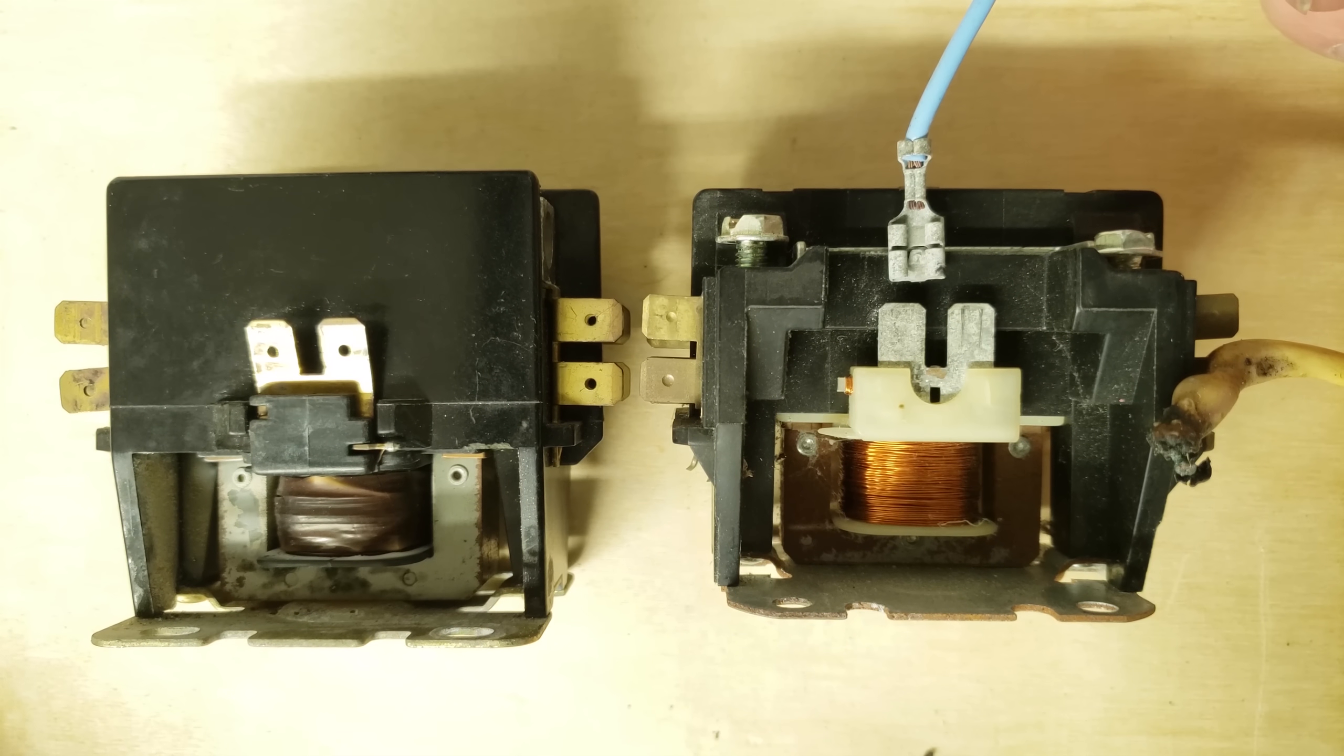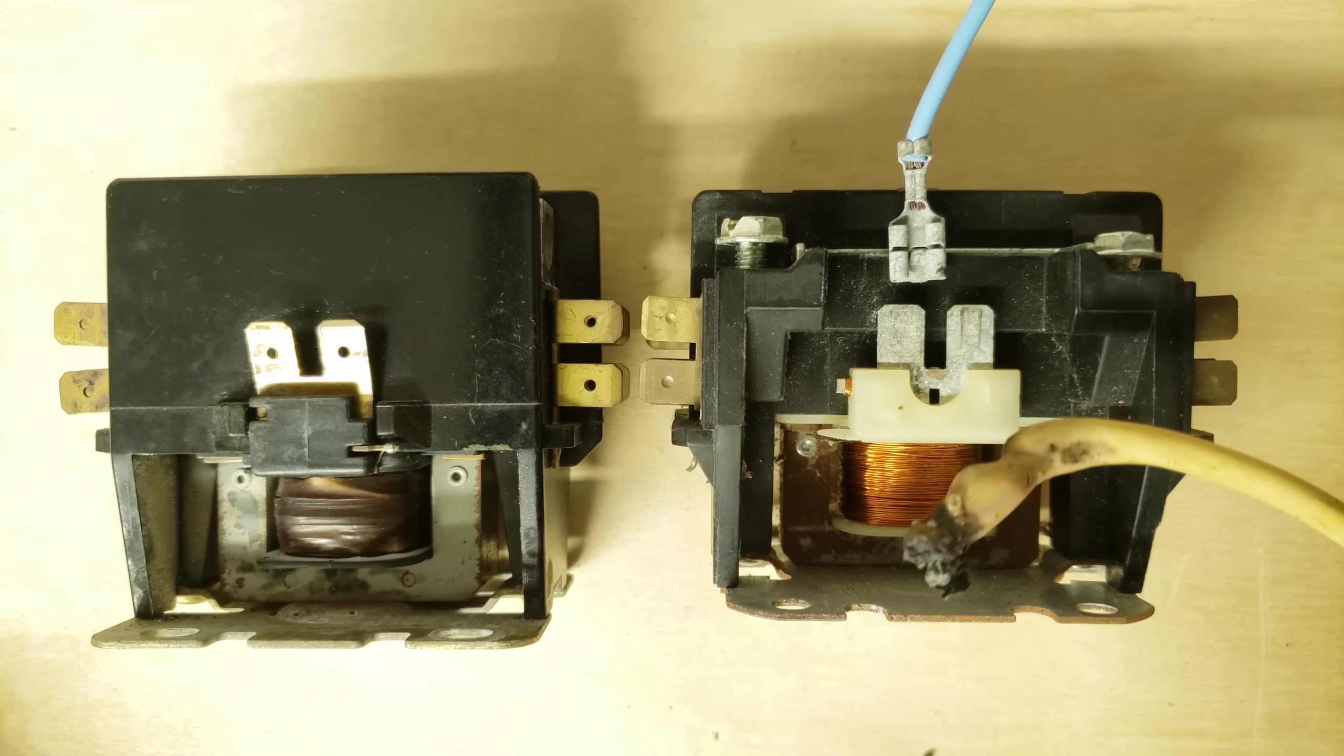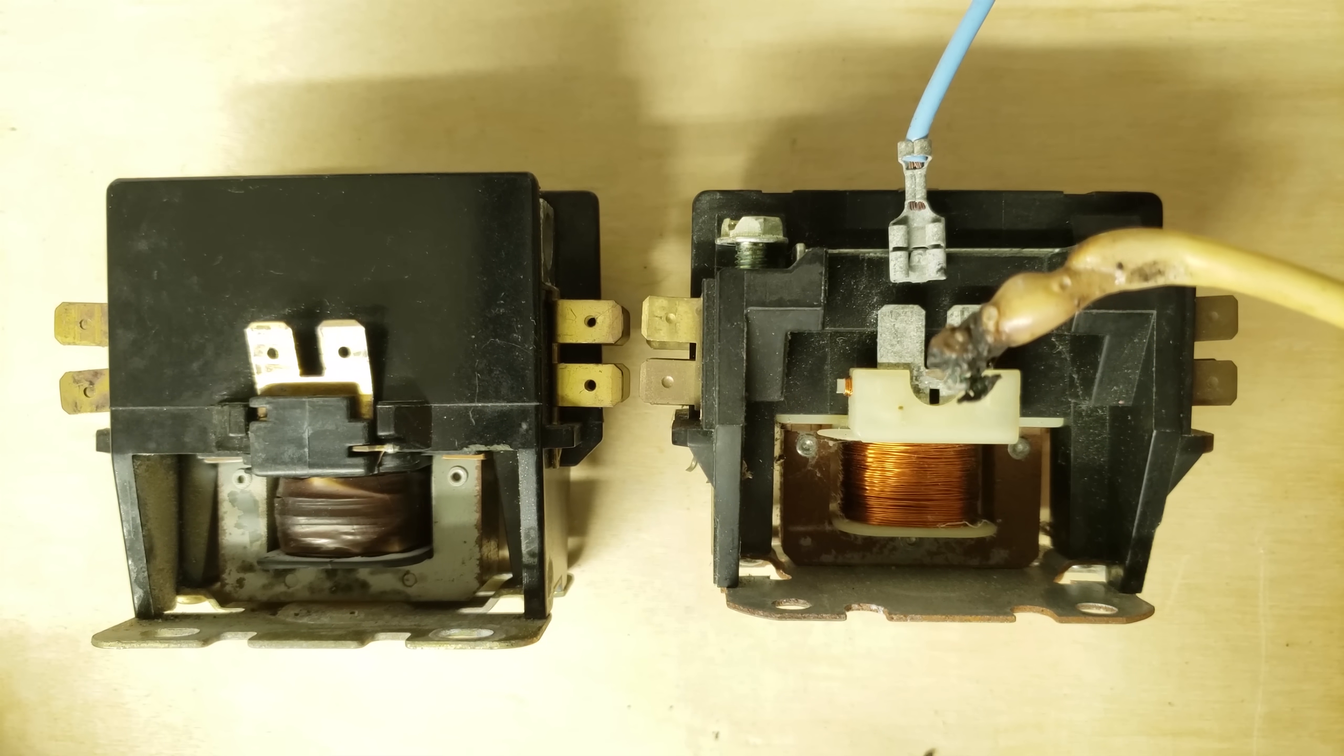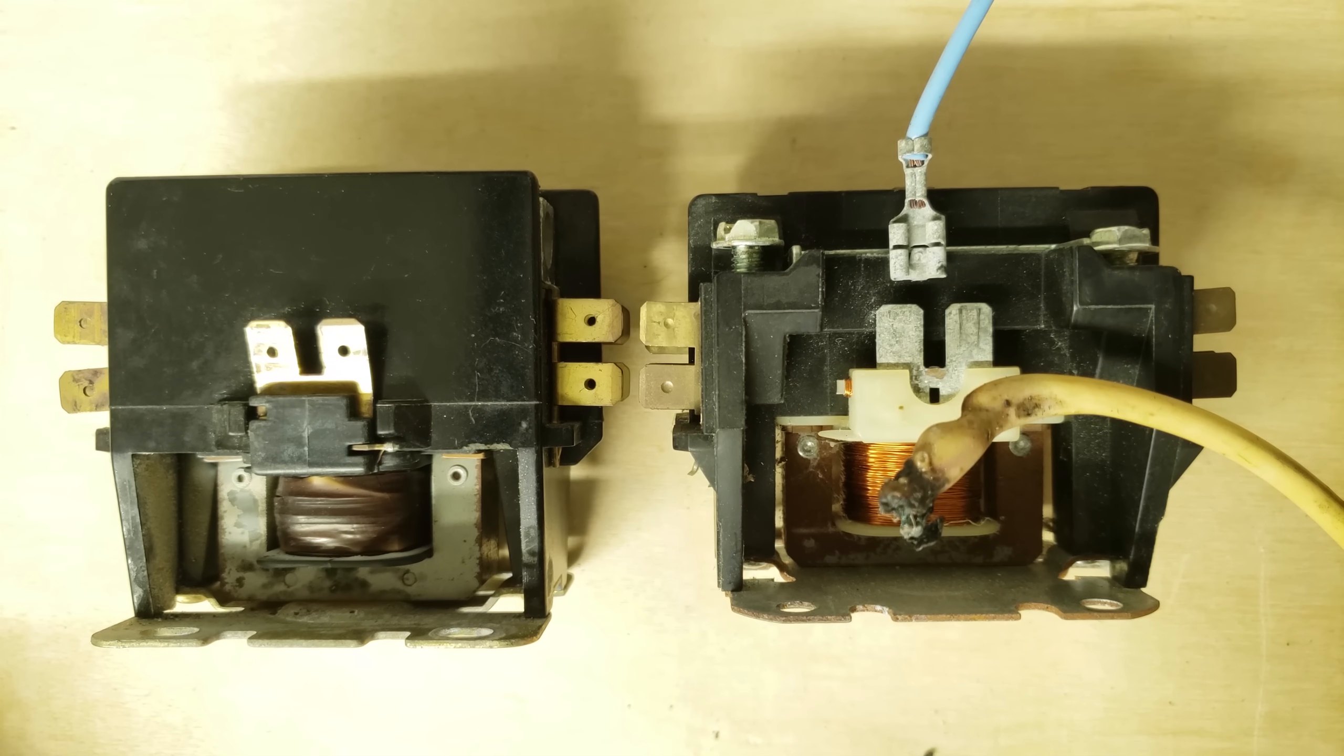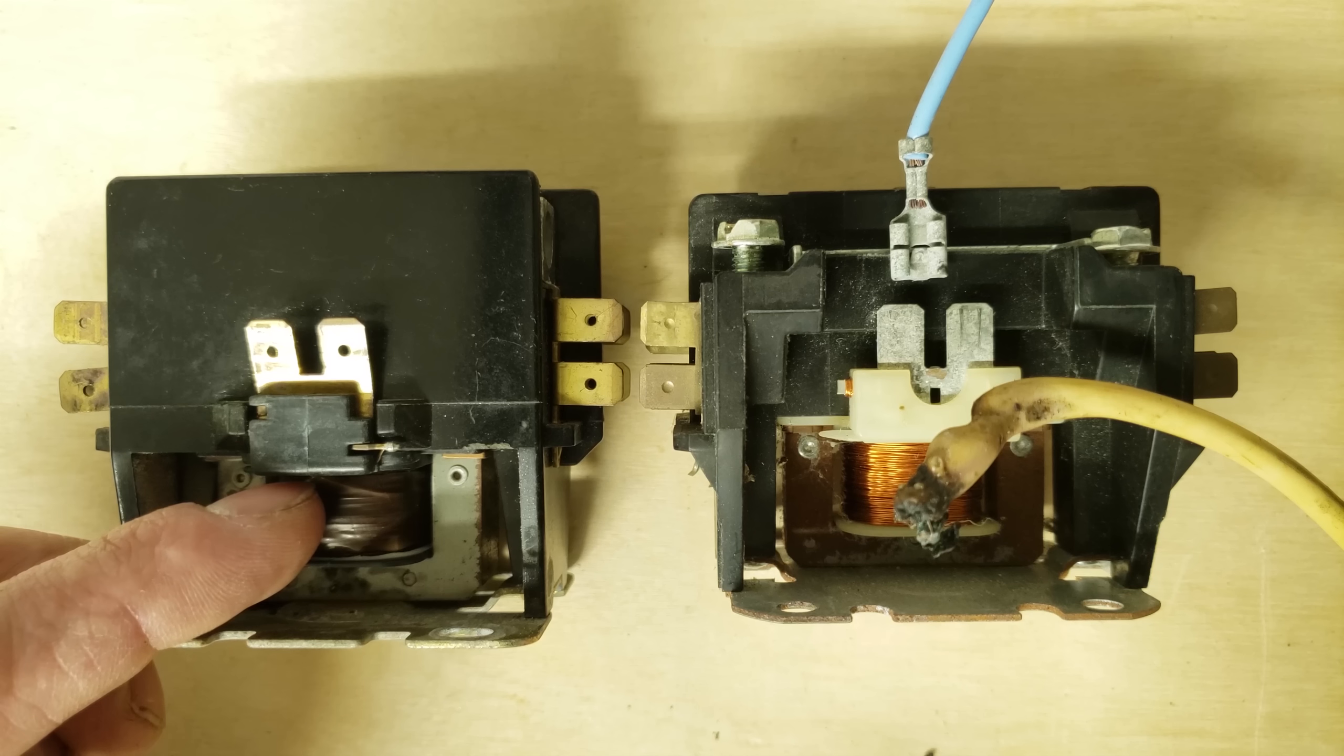You could also have bad electrical connections outside of the contactor such as the line voltage connections like this one right here. You can see this one's pretty burnt out just due to this was a corroded connection right here. You could have several issues, it could be inside the contactor or outside the contactor, but the end result is it might damage the contactor itself in which case you would end up needing to replace it.